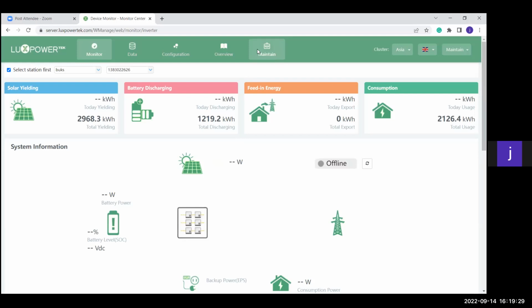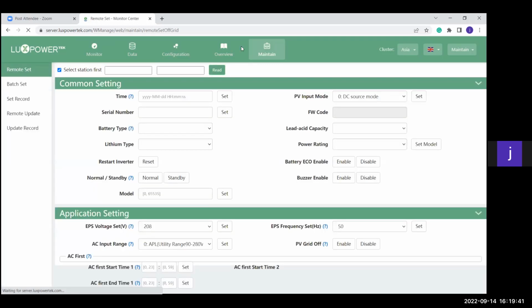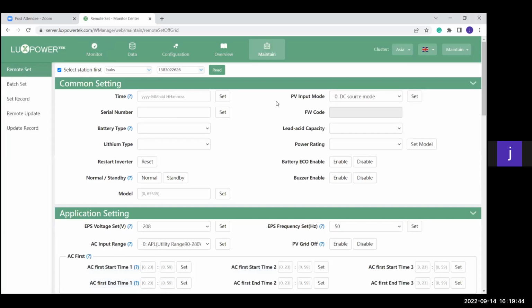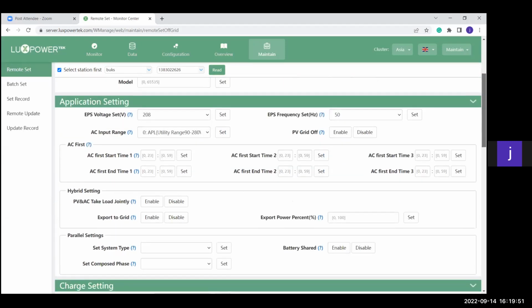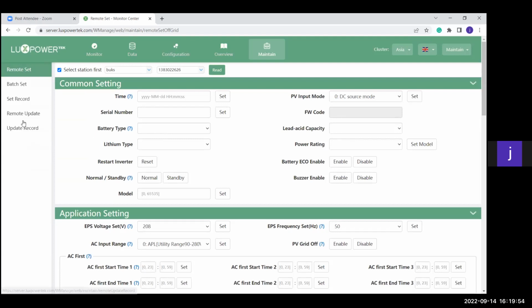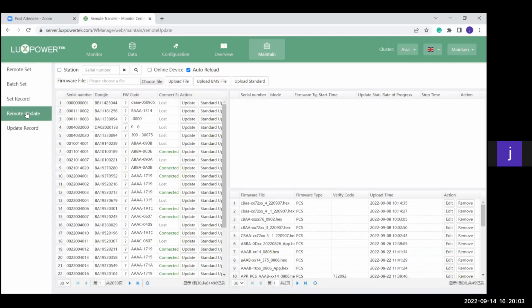From there on, if you are an installer or a distributor's account, you can go to maintain. Once you click on the maintain button, you will see that you have the capabilities to do all the settings on the inverter, the different settings. So you can do all these settings on the account there. Then the most important part of your installer's and distributor's accounts is the capability to update inverters. Once you have an inverter that's in parallel or giving you problems, then you as an installer or the distributor have the access to update the inverter.